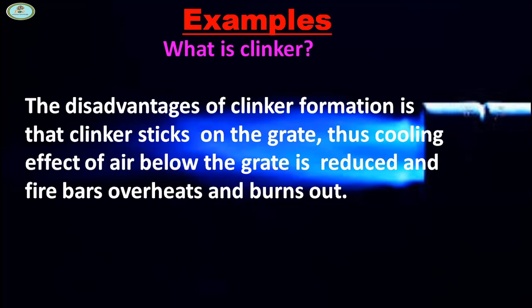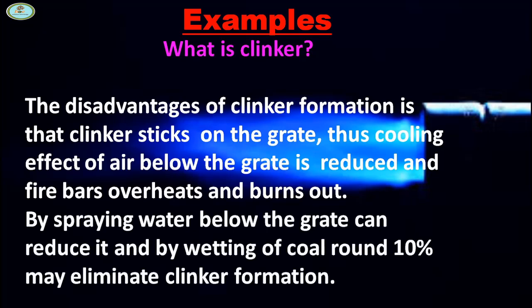The disadvantages of clinker formation are that clinker sticks to the grate, the cooling effect of air below the grate is reduced, and fire bars overheat and burn out. By spraying water below the grate, it can be reduced. Wetting of coal around 10 percent may eliminate clinker formation.